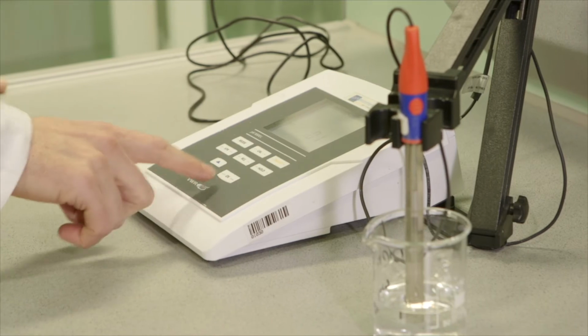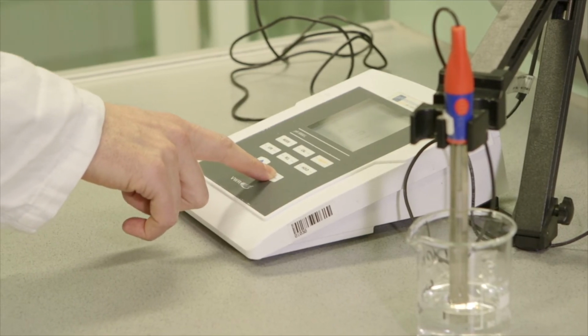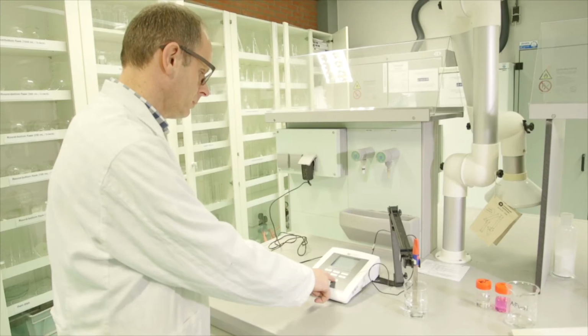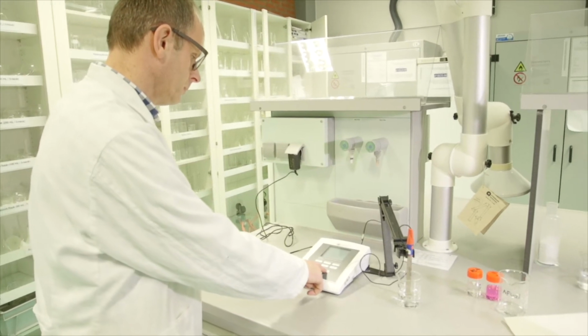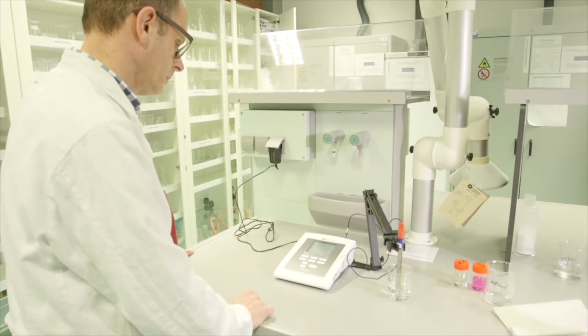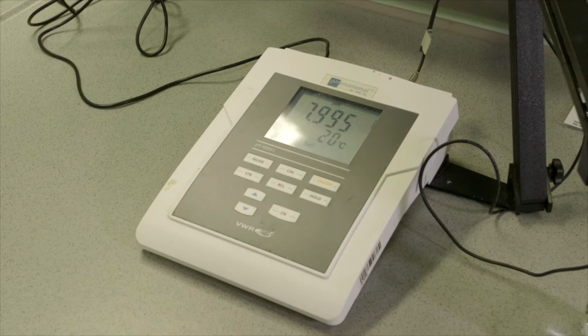The device will ask for the day and time. This is unimportant for measuring pH, and therefore we press 5 times on the OK button. With the mode button, the device can be set to measure millivolt or pH. Since we carry out a measurement with a pH meter, we choose pH. Determine the temperature of the solution and enter this on the pH meter.